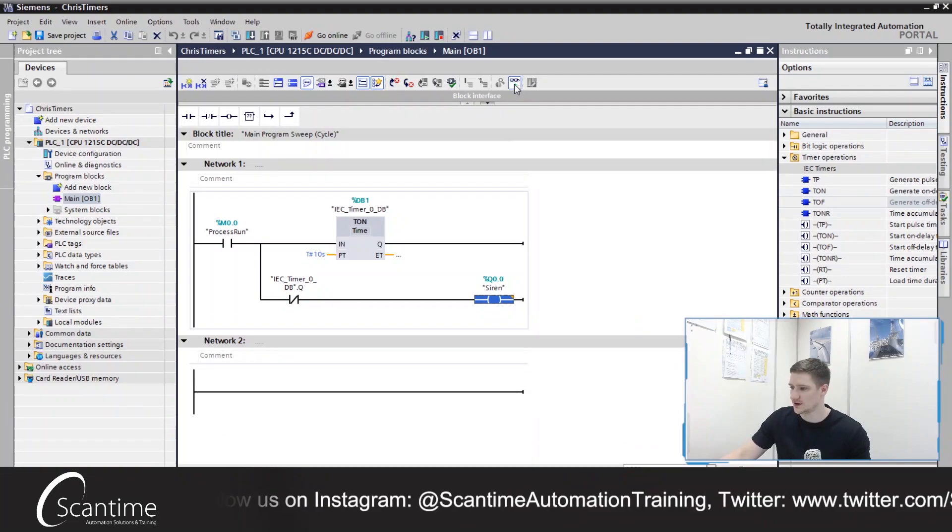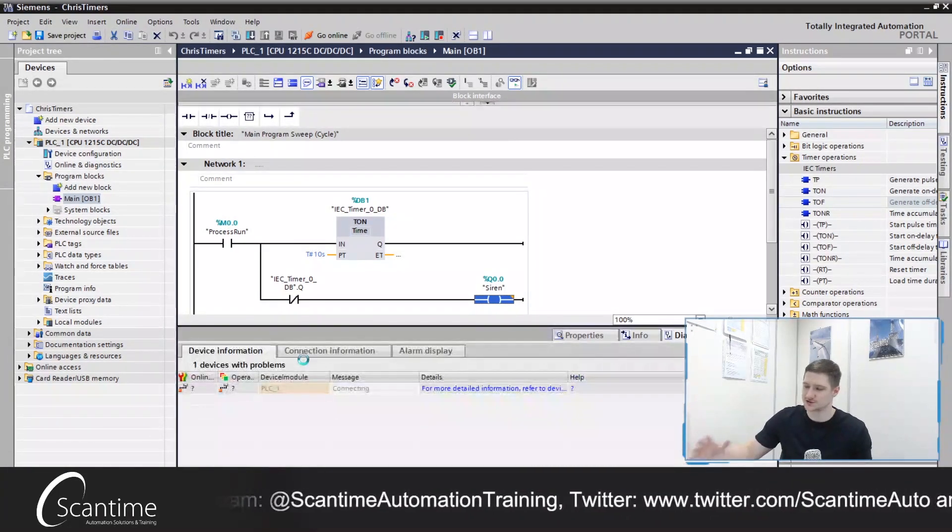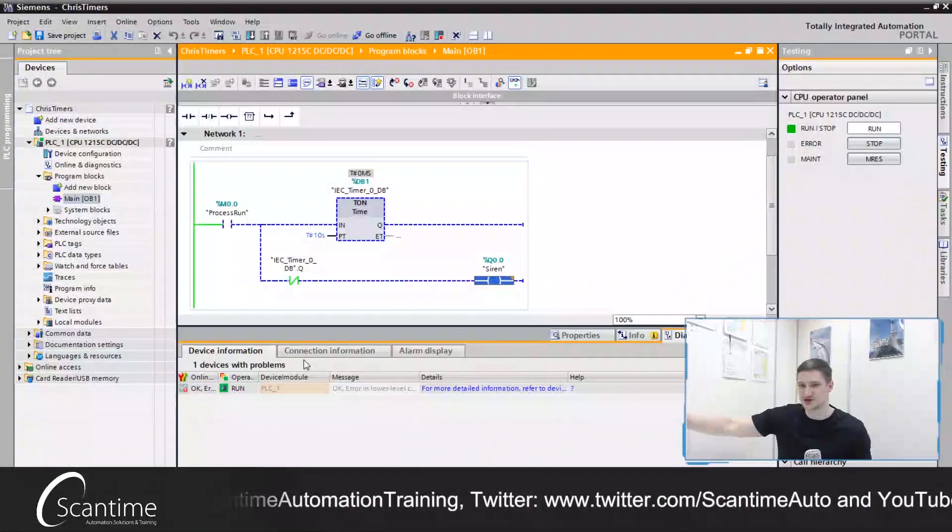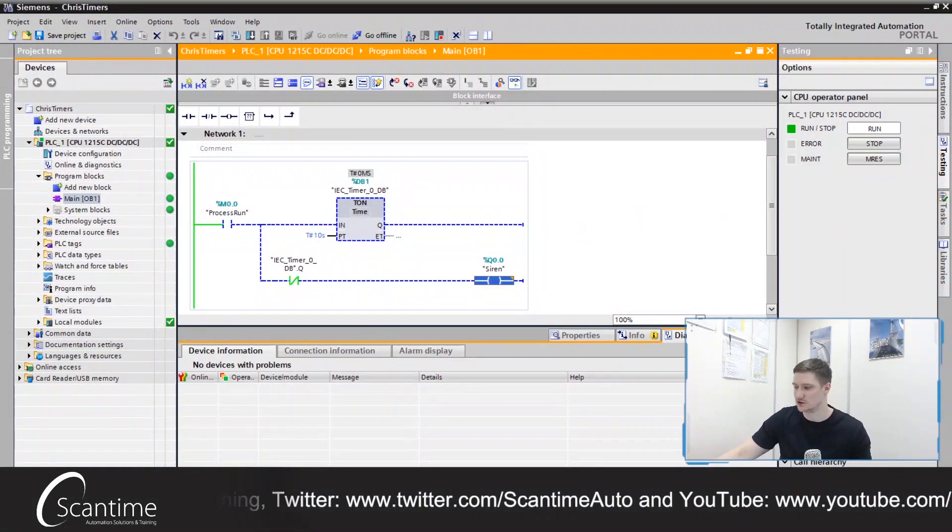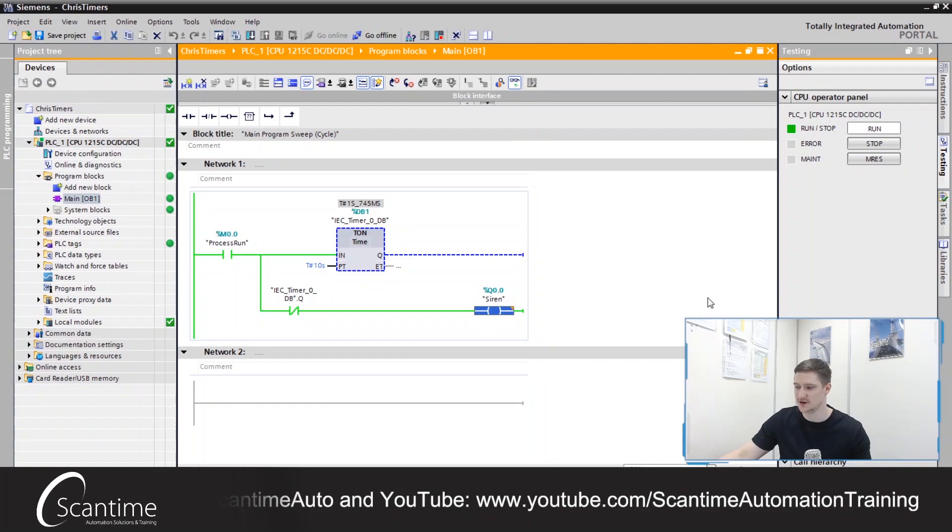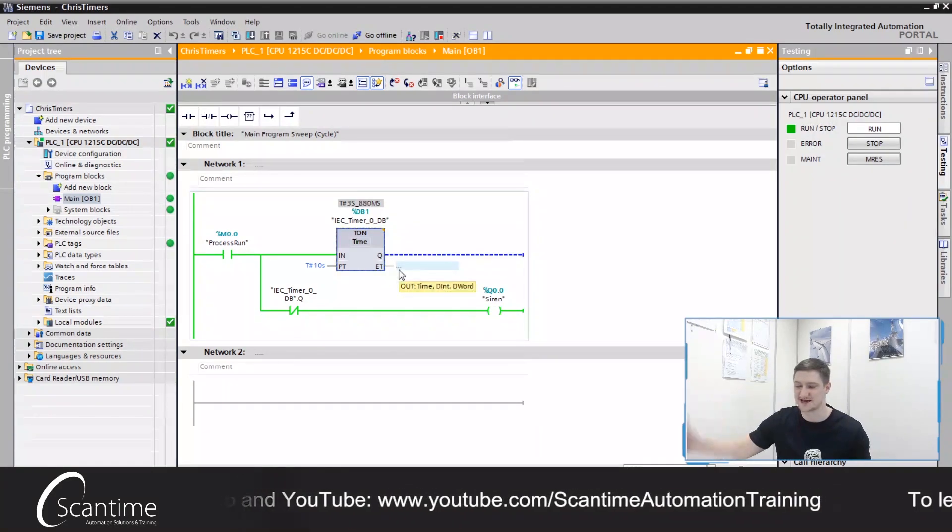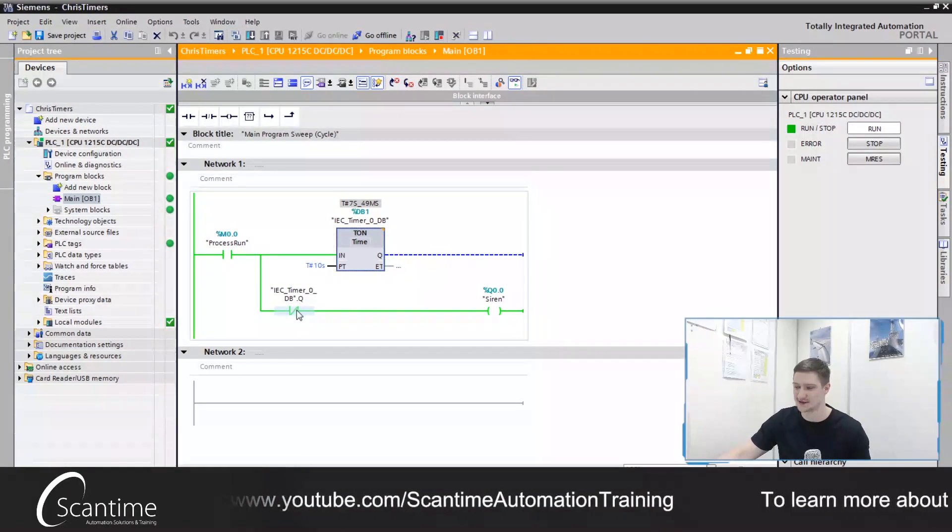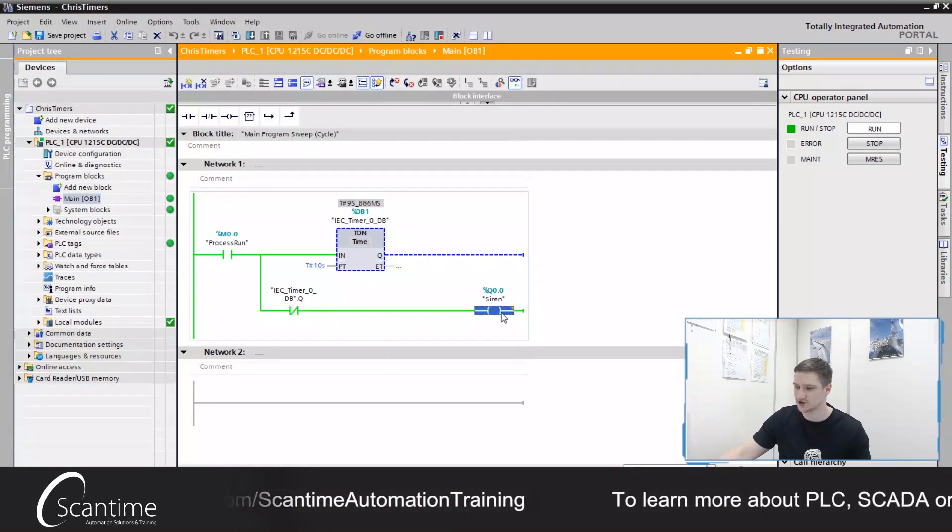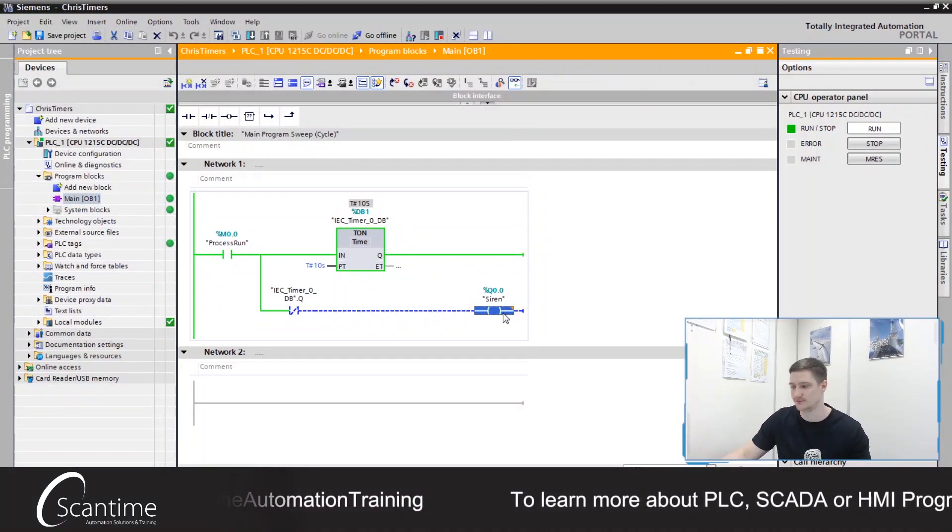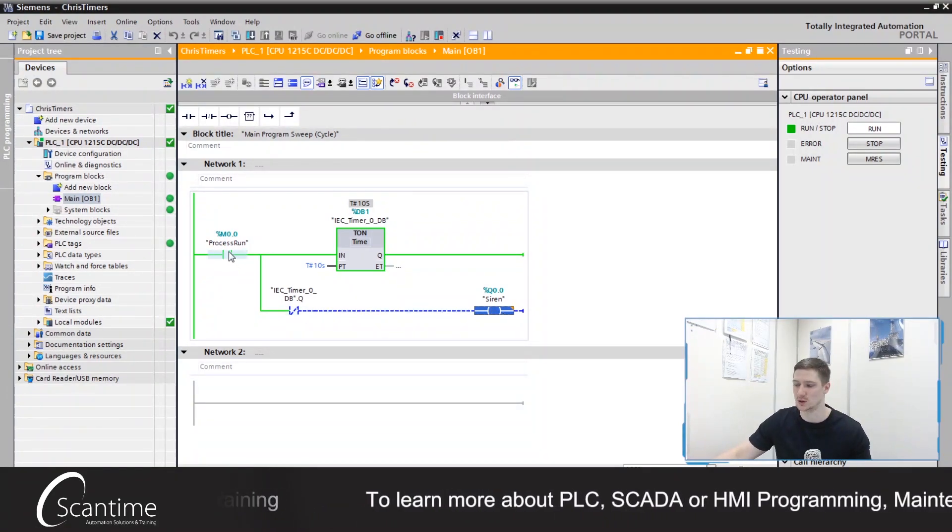Right let's go online. So remember how it works, we turn the process on and the siren turns on. After 10 seconds the siren turns off. So when we trigger the process, the siren turns on and this timer begins to run. After 10 seconds the Q of this timer is going to turn on, this contact will open, turning the siren off. And that there is our timer pulse.